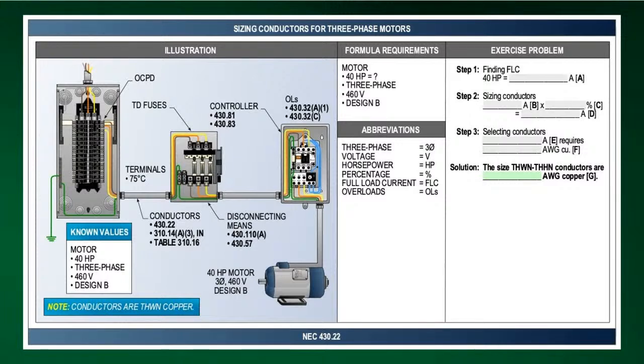The way these illustrations are coming out is unbelievable. When you look at a single motor example, you'll notice we put in time delay fuses. If you look at how we're sizing the conductors coming from that panel board before the disconnect, we're sizing them using 430.22, which is for a single motor.